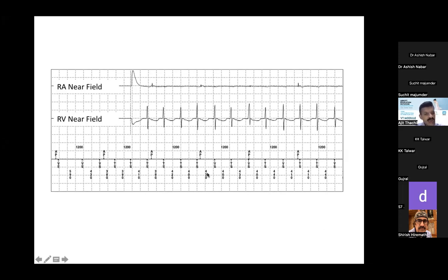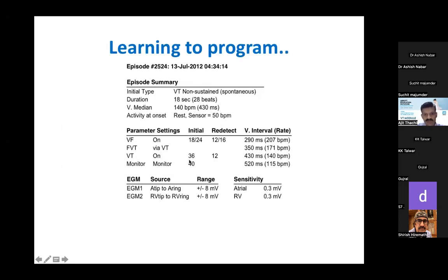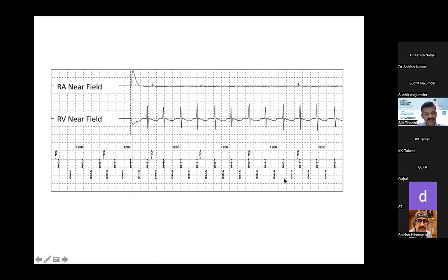Now this is a consecutive count. So how does it count? Remember, this is the count we have to satisfy: 36 beats at 430. So let's see what this device is doing. It's satisfied 1, 2, 3, 4, 5, 6 beats faster than 430. The next beat is 430. So what happens to the count? 1, 2, 3, 4, 5, 6, 0. It goes back to 0. That's how a consecutive count works.